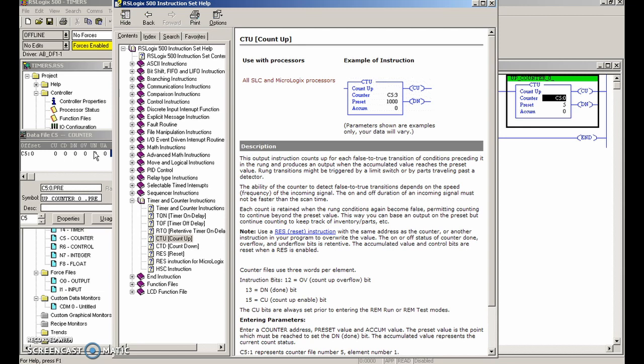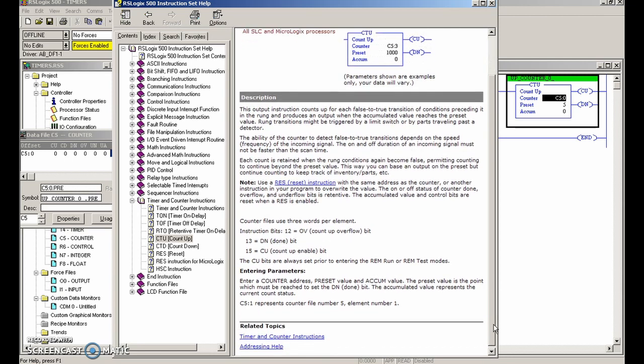We also have UN - that's most likely the underflow. On my cheat sheet, the UN is the underflow bit. The underflow bit will go true when the counter counts below minus 32,768, and the counter will wrap around to positive 32,767 and continue counting down towards zero on successive false-to-true rung transitions. We also have UA - the update accumulator bit - which is used only in conjunction with an external high-speed counter.